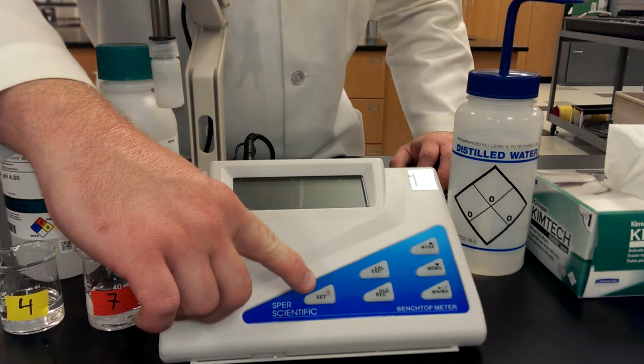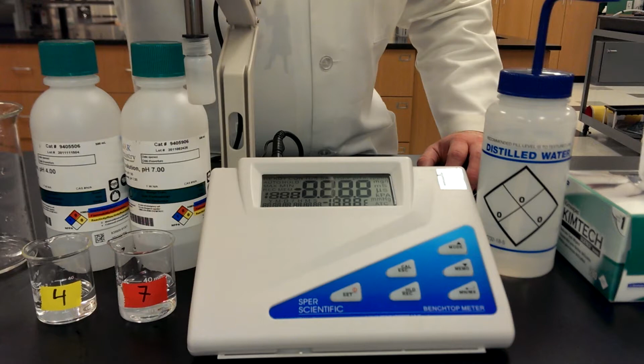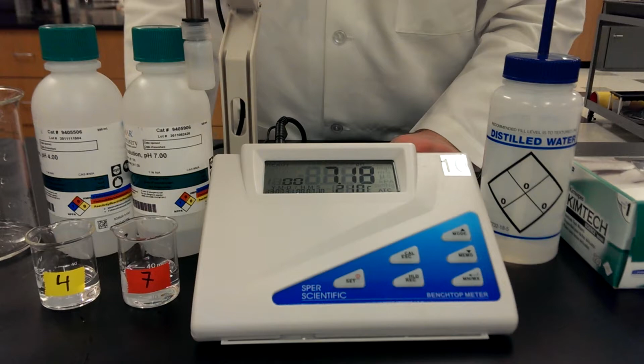Okay, let's get started. First thing you're going to do is push the power button. It's the red circle with the line through it. Hold that down for a second. And you're going to see some numbers up here. That's the pH reading that the probe is actually reading from the solution that's inside this cap. And as you can see, it's not 7.0, and that should always say 7.0 when you first turn it on, because the solution that this probe is kept in should always be a pH 7 buffer solution.